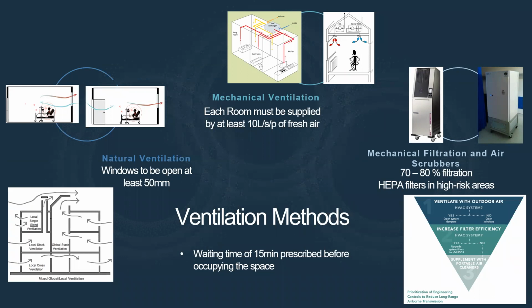Normally what we tend to do in winter times is, it's always quite difficult to manage the patient comfort in a patient room or area, because as soon as you open up the windows, you get the external temperatures inside the room as well. So the minimum prescribed opening of that window cannot be less than 50 millimeters or 5 centimeters. And that's just to make sure that the opening is big enough to actually give you the benefit of the pressurization and the air movement into that particular room.